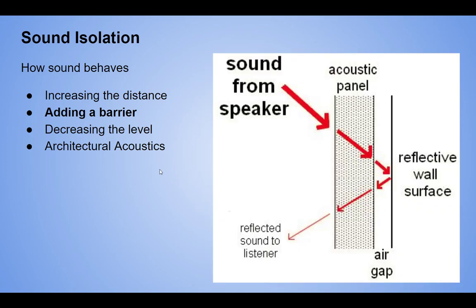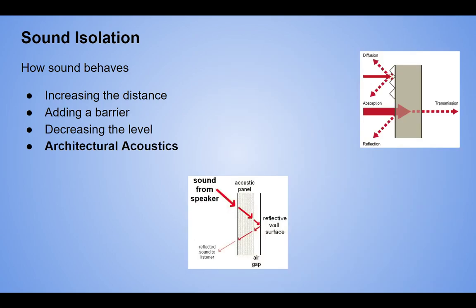Adding acoustic panels on one side of a barrier makes one room quieter, but the maximum you can get from absorption on one side is: in the source space, decrease the level by 6 dB maximum; in the receiving space, 3 dB maximum. It's a trick you can use, but if you have a loud mechanical room, putting a bunch of acoustic foam on the wall will not fix that.